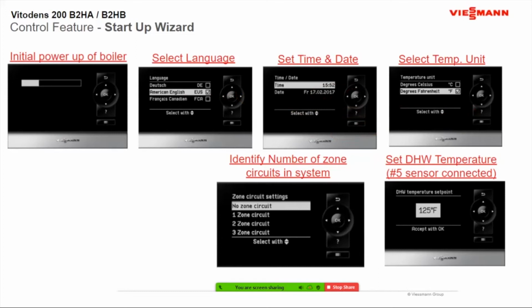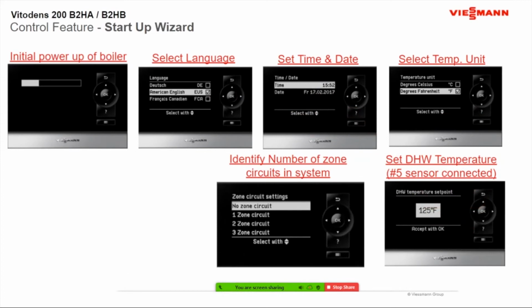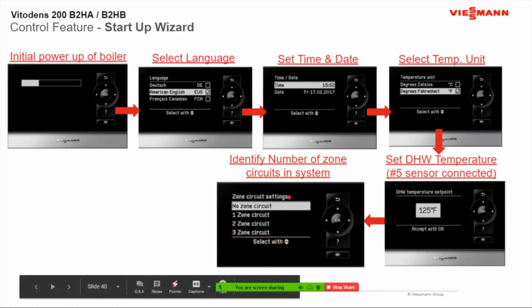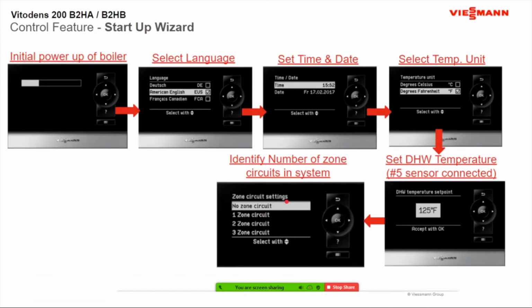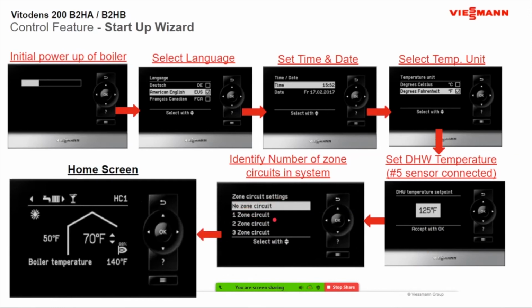If you're doing domestic and you plugged in the number 5, it will ask you to set up your domestic set point as well. So you don't even have to go into settings and do this. It'll come up automatically. If you're not doing domestic, it will bypass this portion and go right to the next part. Next part, if you're doing the older way of heating circuits, you're going to click no zone circuits, and it's going to give you heating circuits. So say you're controlling 2 of our mixing valves, you're going to have heating circuits. Remember, they have their own pump, so you're just going to control the heating curves for those. So you're going to go in here and set up heating circuit 1, 2, or 3.